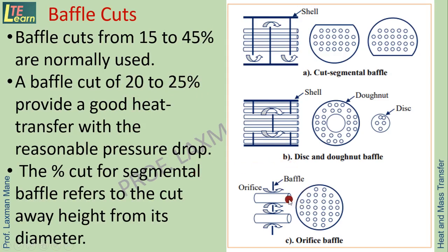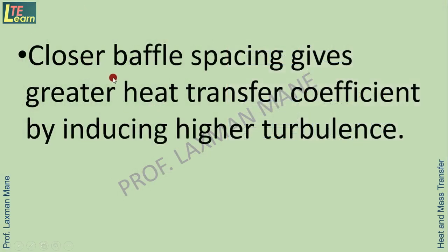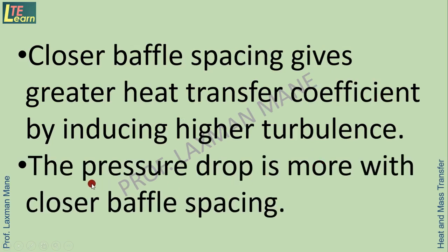The percent cut for a segmental baffle refers to the cut away height from its diameter. So here you can see these cuts are taken in the baffle, either on the upper side or the lower side of the diameter. Closer baffle spacing gives a greater heat transfer coefficient by inducing higher turbulence, but the pressure drop is more with closer baffle spacing, meaning there will be more baffles, which will increase the resistance to the flow of fluid.